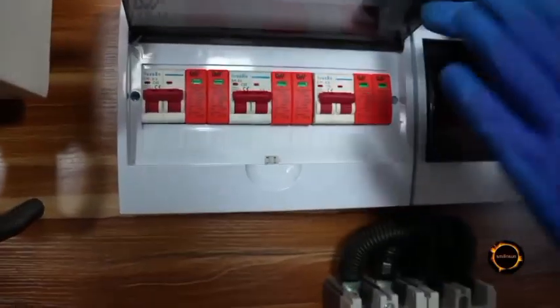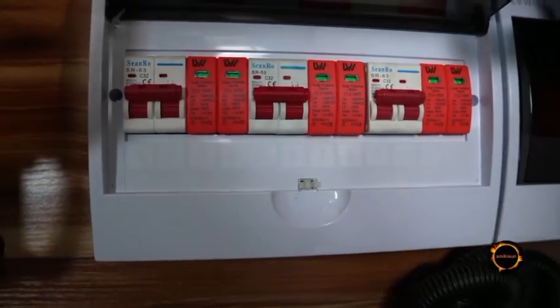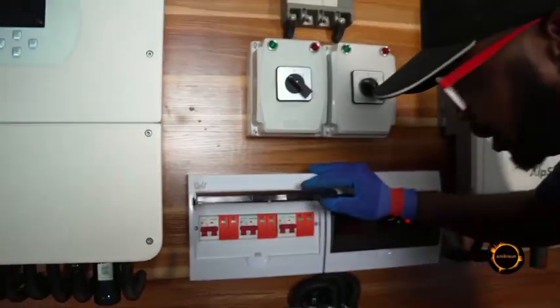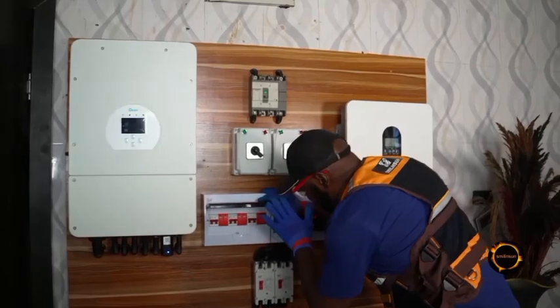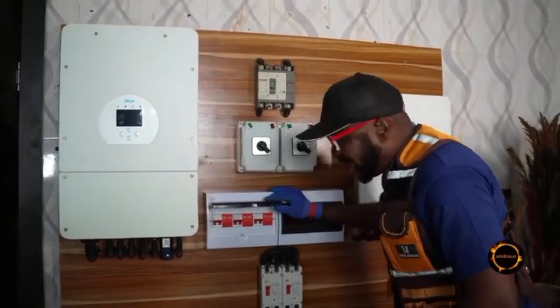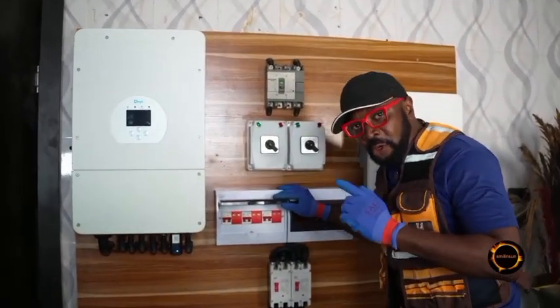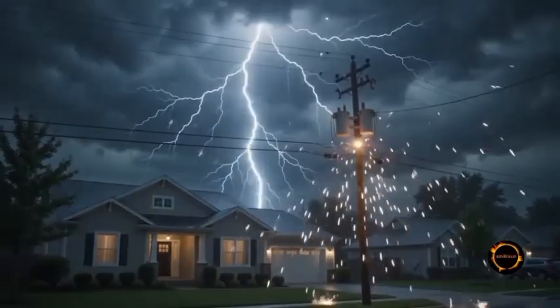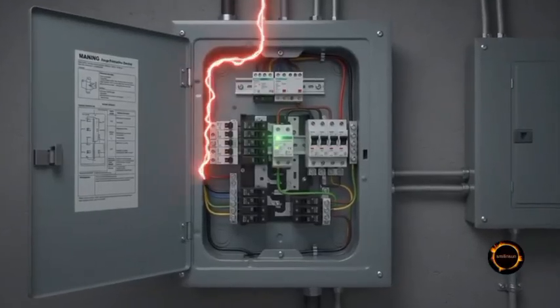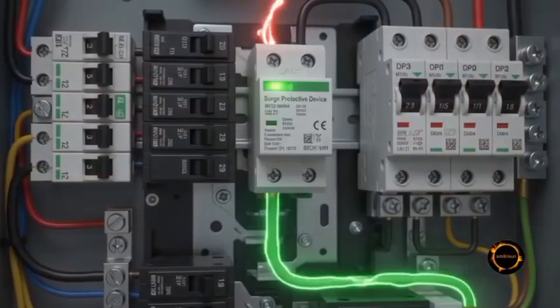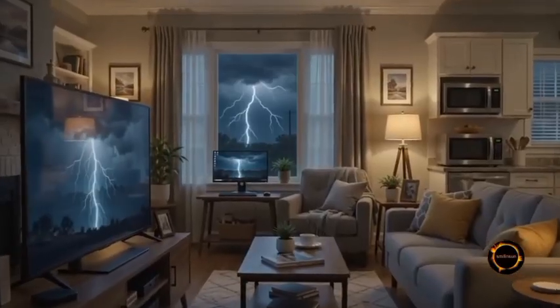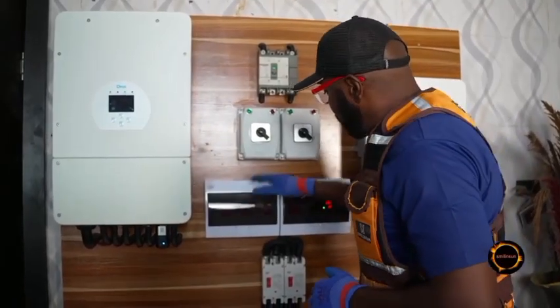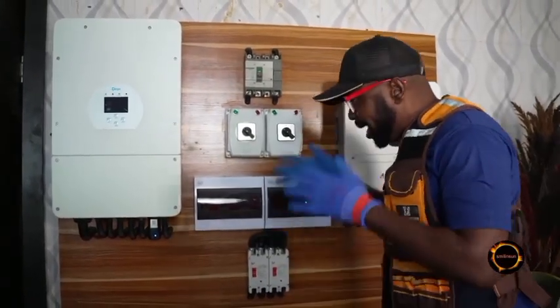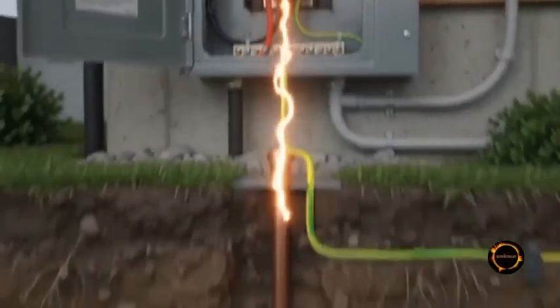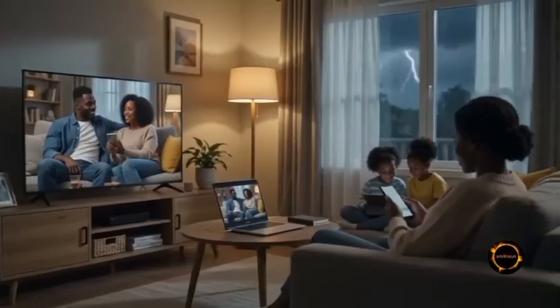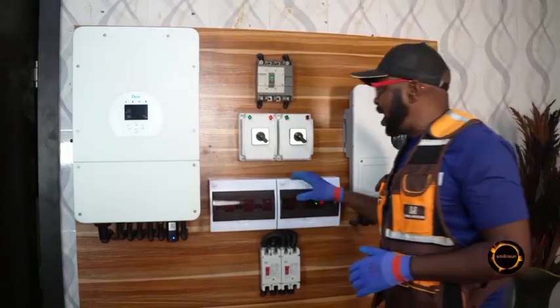devices, right? I have 4 of them right here because I have 4 strings on my solar system, right? So the job of the surge protection devices is to stop anything it deems to be a surge from gaining access into this system. It will deflect the surge or the high voltage or the high current that is coming from the lightning. It will deflect it all the way through the earth connection, the earth line, into the earth installation that you have on the ground. So right in the earthing installation, it's safe, it stays there, it doesn't harm the system.